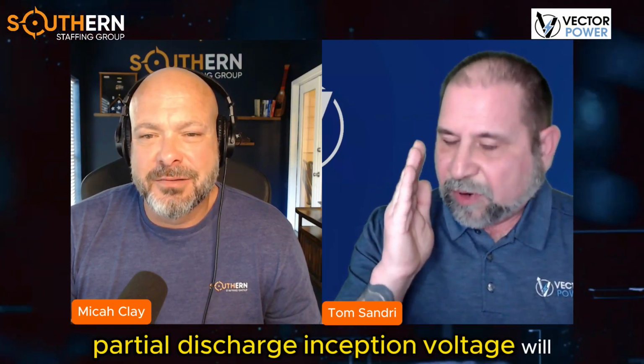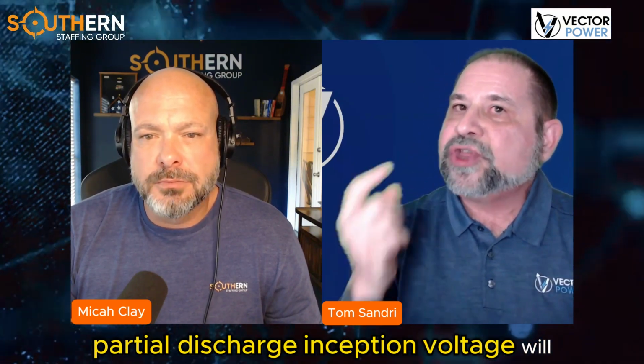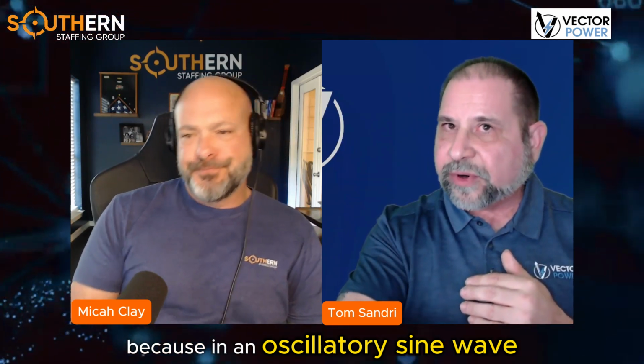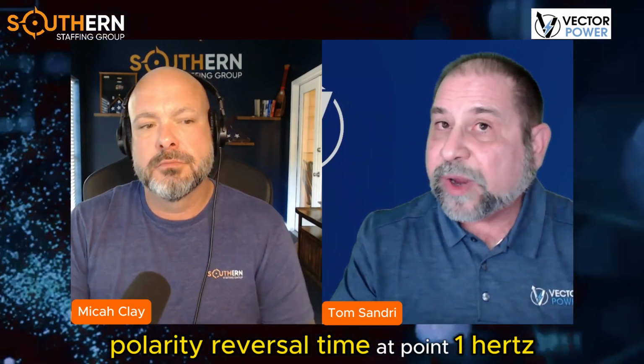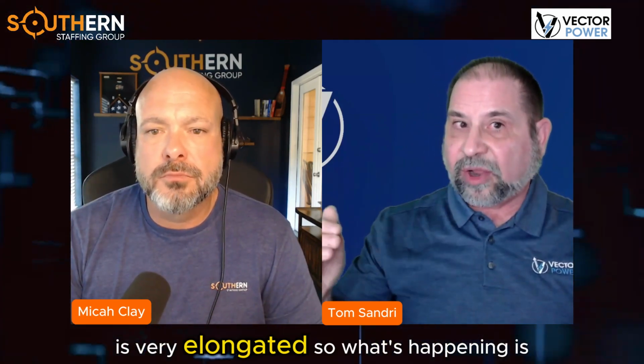Stay away from that 0.1 hertz, man. Oh my God, stay away from it. The partial discharge inception voltage will not correlate to 60 hertz because of the loss factors, because in an oscillatory sine wave, the ramp up time and the polarity reversal time at 0.1 hertz is very elongated.